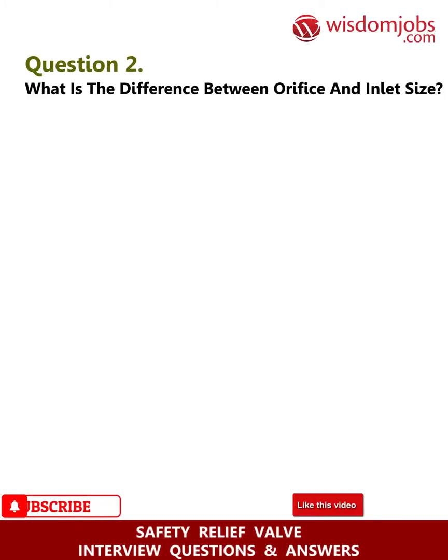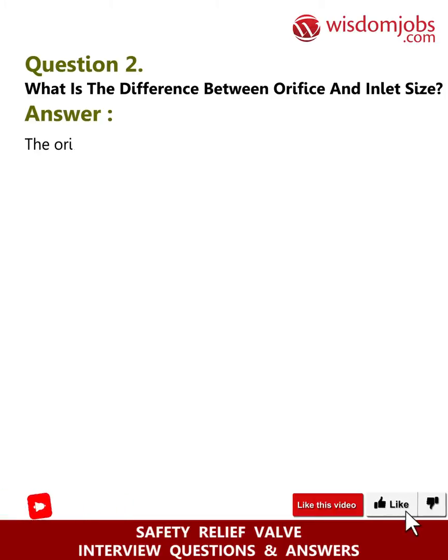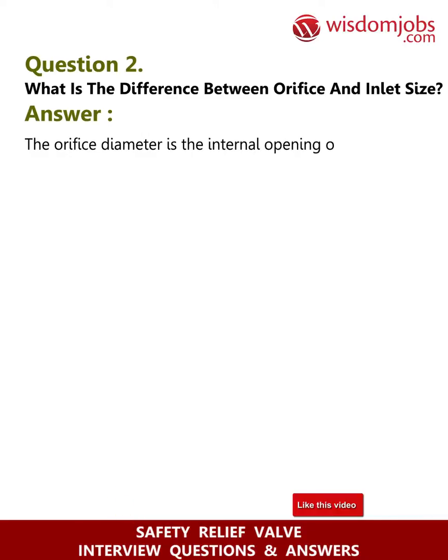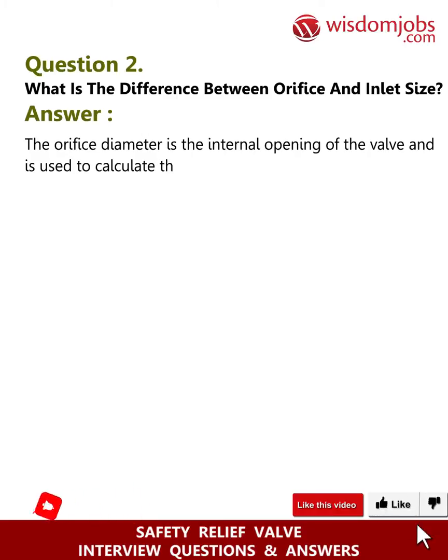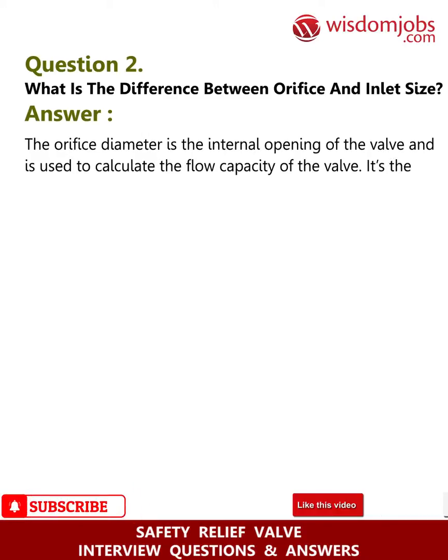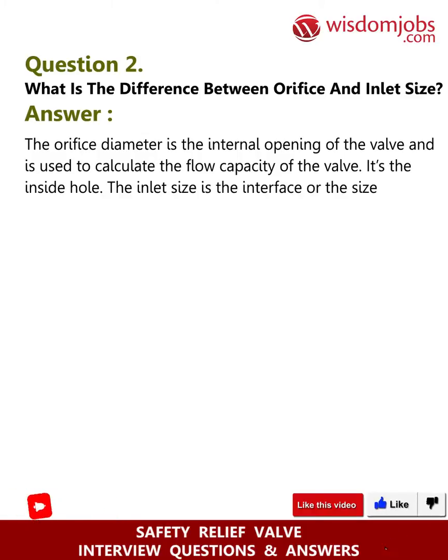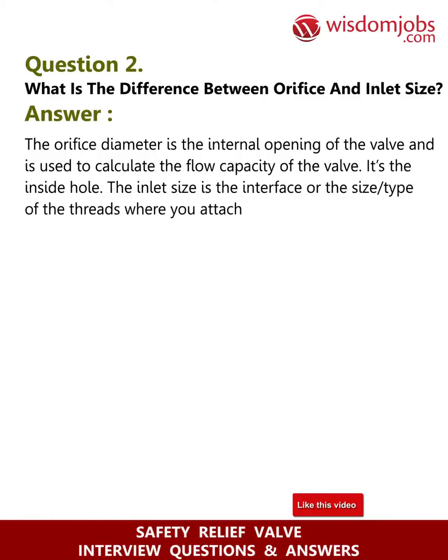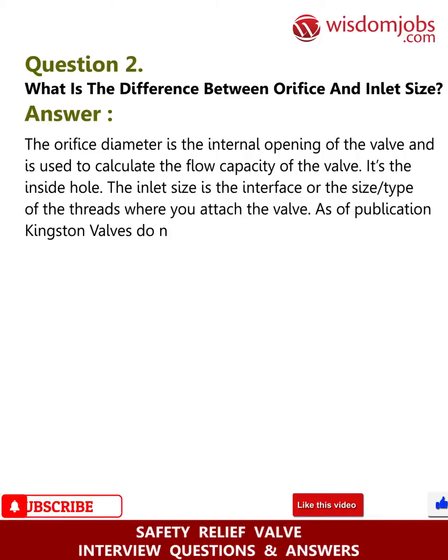Question 2: What is the difference between orifice and inlet size? Answer: The orifice diameter is the internal opening of the valve and is used to calculate the flow capacity of the valve — it's the inside hole. The inlet size is the interface, or the size and type of threads, where you attach the valve.